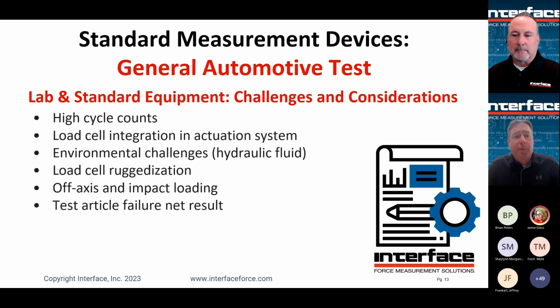And then we don't want to think this is going to happen, but it should be considered. You're testing something, that something could break. What happens when that device under test does in fact fail? Is there going to be some sort of a ring occur in the load string? Some sort of a reversal of load, perhaps? Perhaps you've got something tied up in tension very tightly and it fails. What happens to that load string under that failure? You're going to get a ring back into the load cell. Is it going to push the actuator and the load cell into the ground? And of course, that's also another safety consideration: what happens when this fails? Do we have safety provisions in mind to make sure that the most important thing, that people are not injured, is protected through an event of that type?